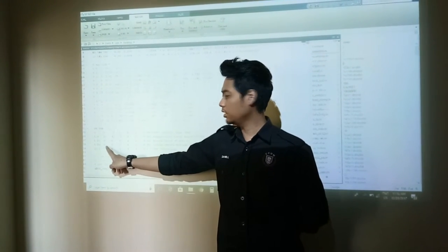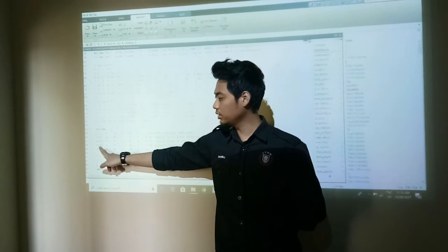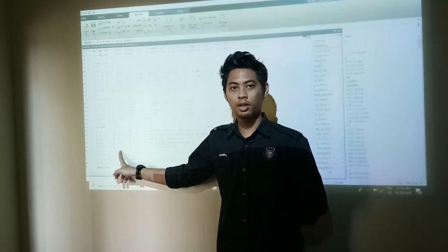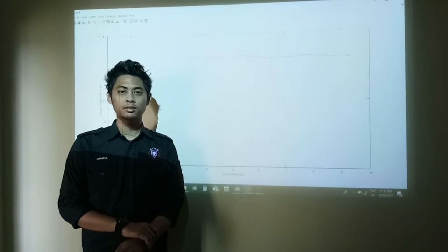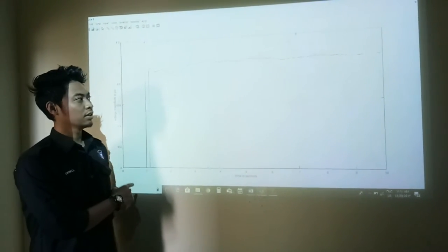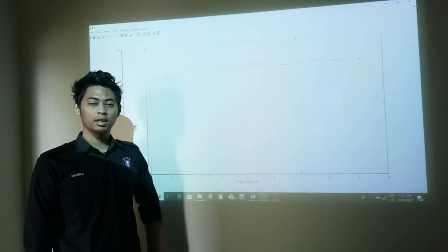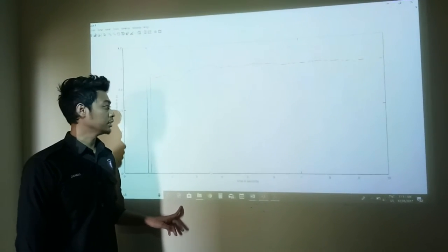For the stable case in our system, we apply 1.16 seconds as our stable condition when we run the system in the network. So for my case, which is the stable case, one of the four stable study cases that I will conclude, this is the voltage magnitude of the wave after we apply the fault at bus 10 and bus 32 in the 145 bus system network.